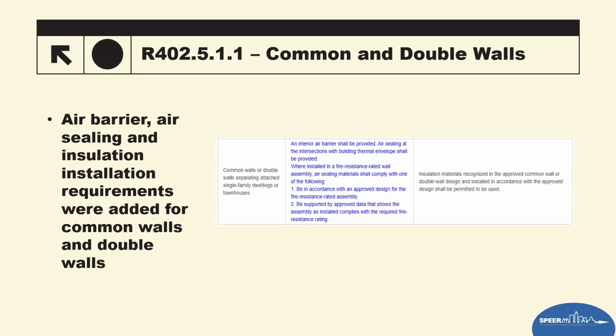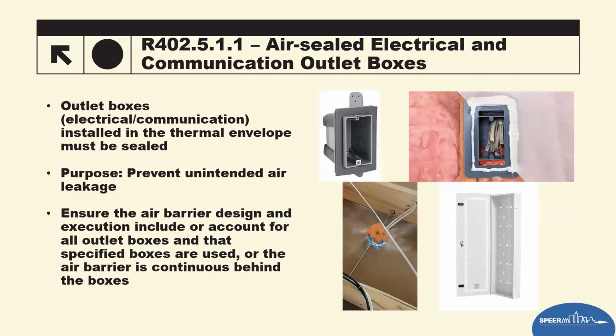That again was an issue in the field with me doing townhomes and the like, is you've got these common walls that are added to that, and suddenly it's an argument of, well, that's not an exterior wall, that's something different. They've now defined it in the code and added it to the checklist table. Air-sealed boxes continue to be a contention in the code. I laugh about it because every single cycle they've updated this over and over again. Really, the end result is you either use a manufactured airtight box, and if you do, it has to be NEMA OS4 tested. Same thing as using a can light, has to be ICAT rated and has to be rated as such to be air tested.